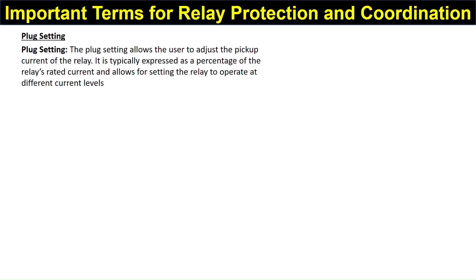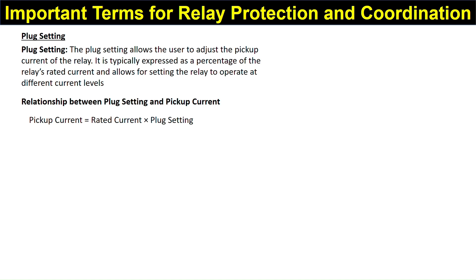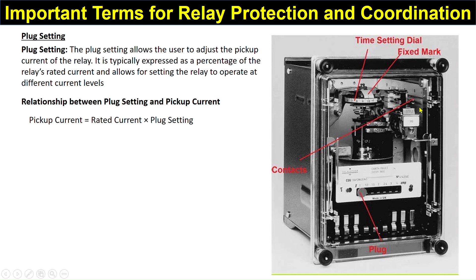Plug setting allows users to adjust the pickup current of the relay. It is typically expressed as a percentage of the relay's rated current and allows setting the relay to operate at different current levels. The pickup current equals the rated current multiplied by the plug setting. On the relay, the time dial (TMS) setting and the plug setting are adjusted at separate locations.